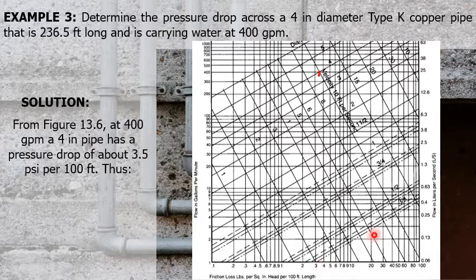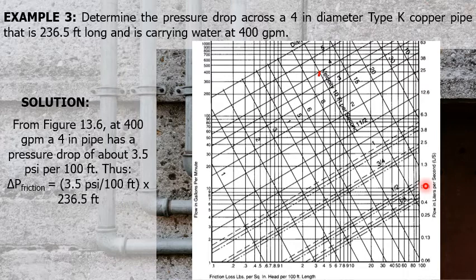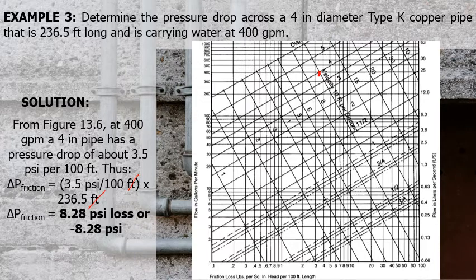From Figure 13.6, at 400 GPM, a 4-inch pipe has a pressure drop of about 3.5 psi per 100 feet. Thus, to compute for the pressure drop, we simply multiply 3.5 psi per 100 feet times the length of the pipe, which is 236.5 feet. This unit will be cancelled. Calculating, that is equal to 8.28 psi loss, or negative 8.28 psi, which is the pressure drop.